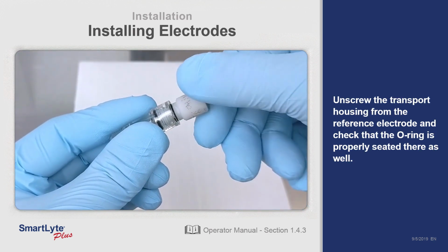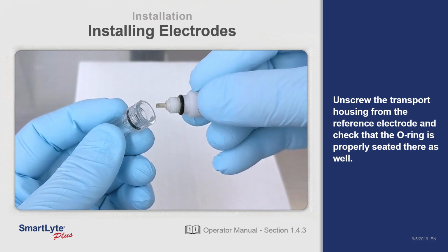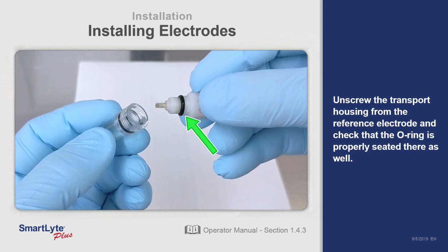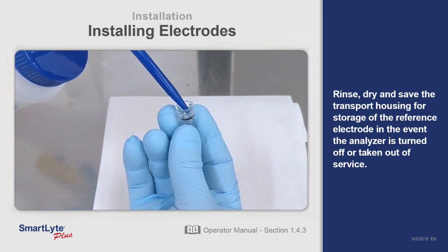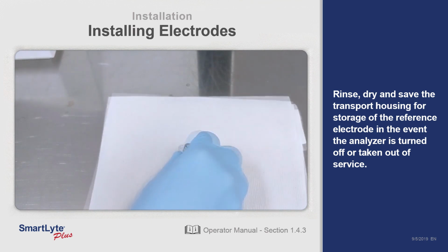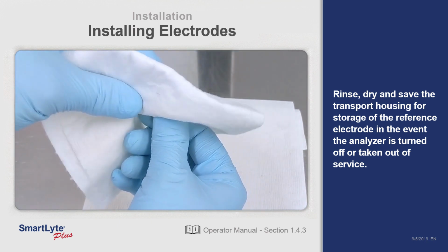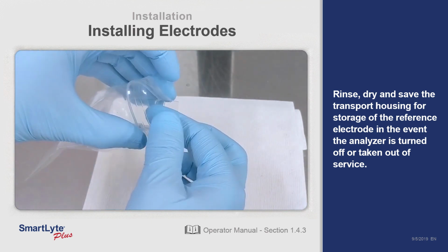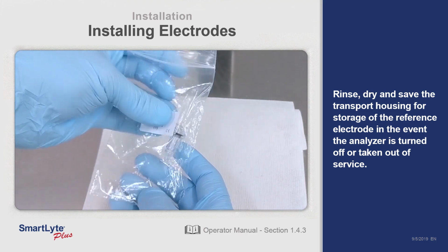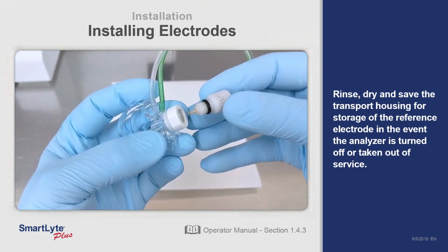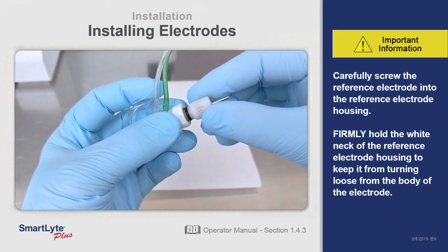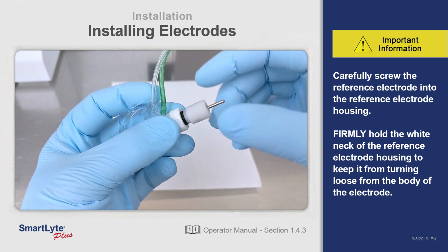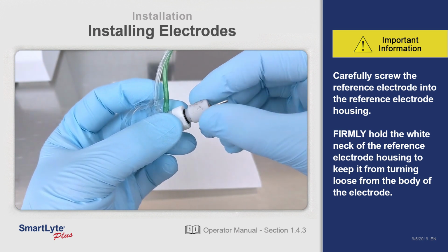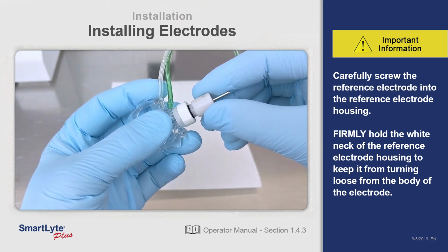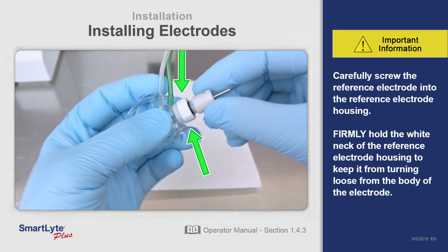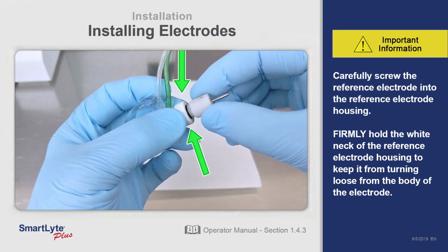Unscrew the transport housing from the reference electrode and check that the O-ring is properly seated there as well. Rinse, dry, and save the transport housing for storage of the reference electrode in the event the analyzer is turned off or taken out of service. Carefully screw the reference electrode into the reference electrode housing. It's important to note that when screwing the reference electrode into the reference electrode housing, you hold the white neck of the electrode.